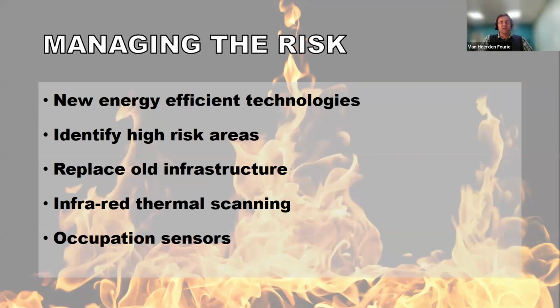One method is just to go and replace all your old light fittings. Another method is to do infrared scanning, and one of the interesting facts we picked up was that there were quite a number of loose connections, almost like dry joints, in the light fittings that were showing a higher than normal thermal footprint, so that you can address. Then there's the installation of occupation sensors in unoccupied areas to make sure the lights are not energized when there's no people in the area.